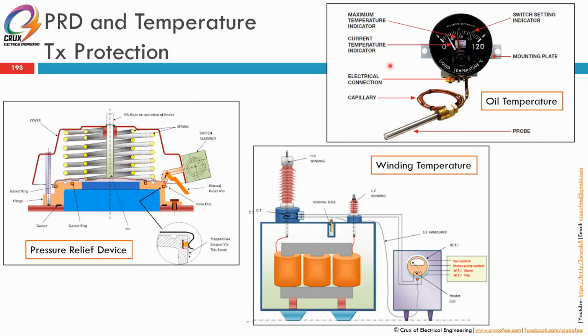Alright. Then we have here our oil temperature. This is the probe. Then capillary connected directly to the temperature sensor, the temperature indicator. So the temperature indicator is from 0 to 120. So our transformer, normally if it's a paper-based transformer, it's a class A. So normally the maximum temperature rating allowed is up to 105 degrees, or 100 degrees. So it depends on the temperature class of the transformer.